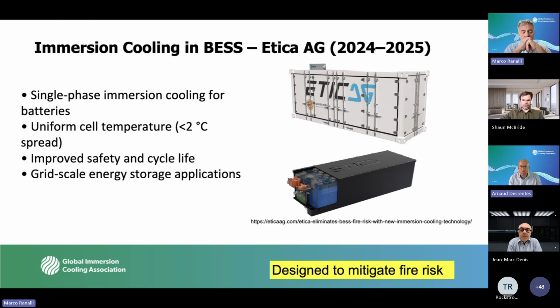Yeah, sure. So it's a good transition between the on and off-road applications and the data centers. This application, the battery energy storage system, is a stationary application, and there were a lot of fires that happened in China, especially in the last 3 years. So regulation went stricter a year and a half ago, and then there was a big move from air cooling for the BESS to immersion cooling.